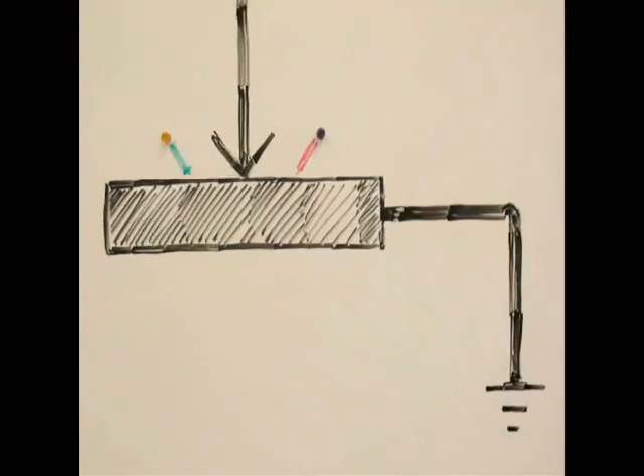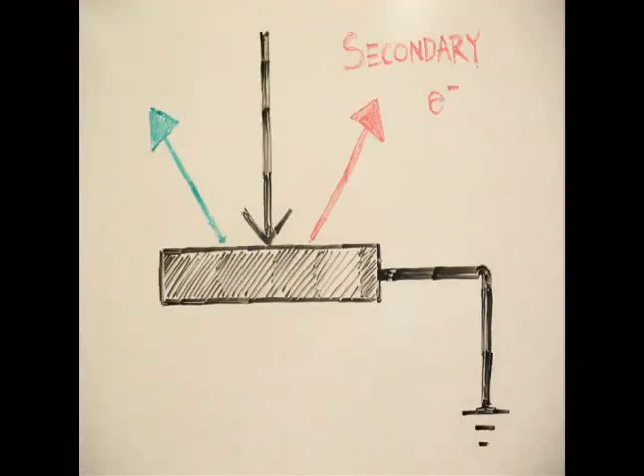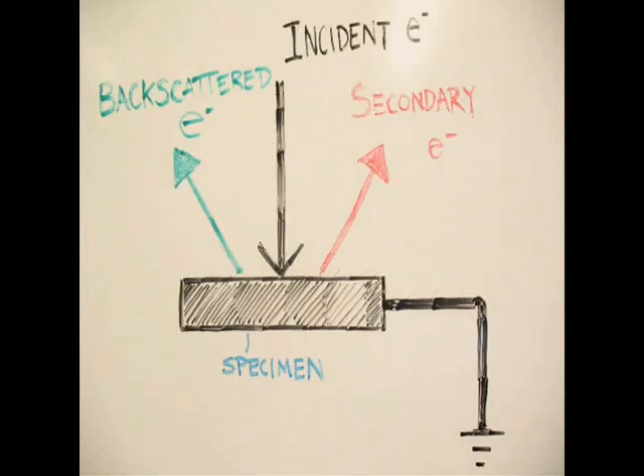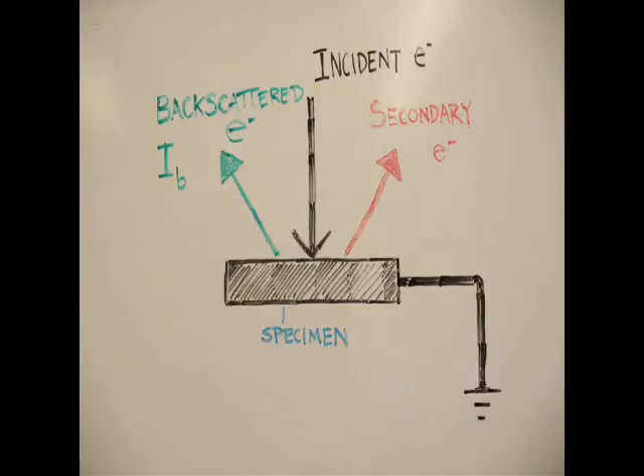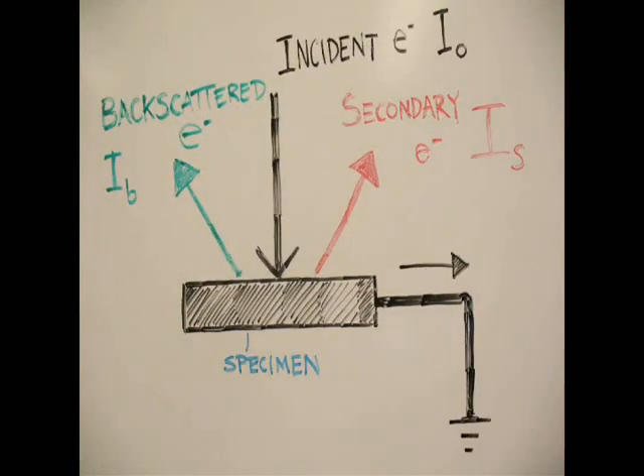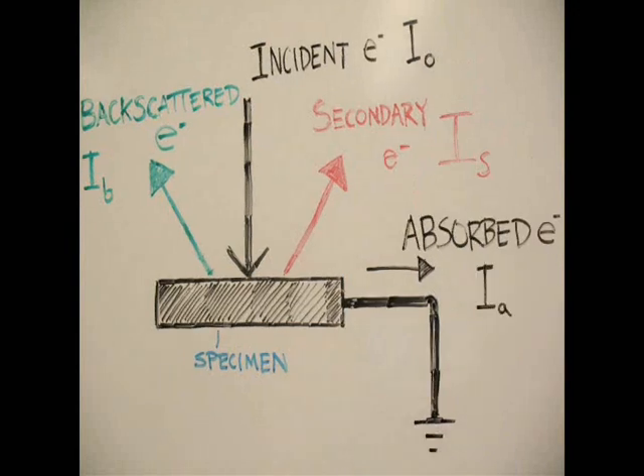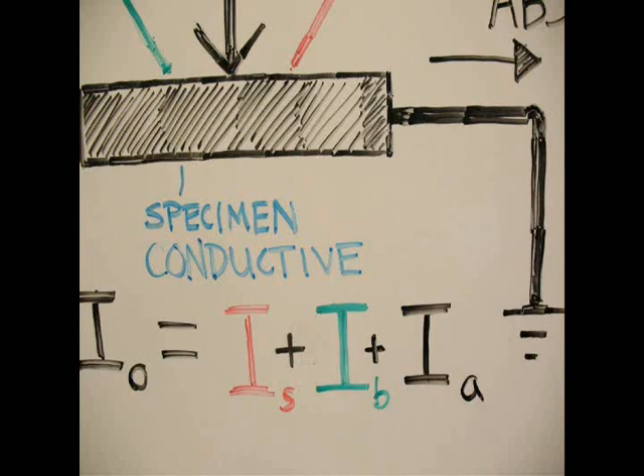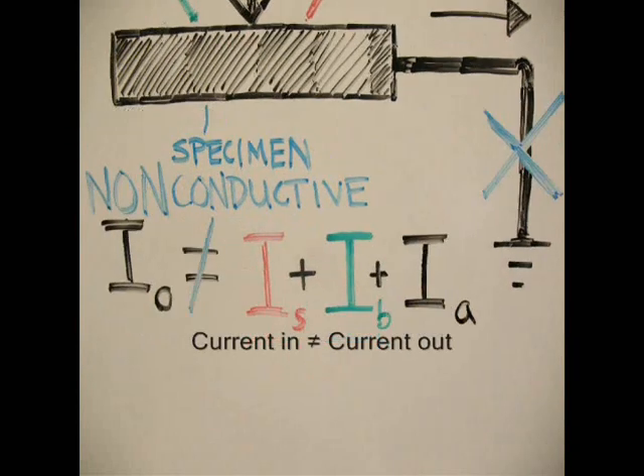Current in must equal current out. This occurs when the specimen is grounded via a conductive path. A conductive path can be provided by a sputtered coat or copper tape. When the specimen is non-conductive, electrons cannot escape and build up in the specimen, which can overexpose the image.